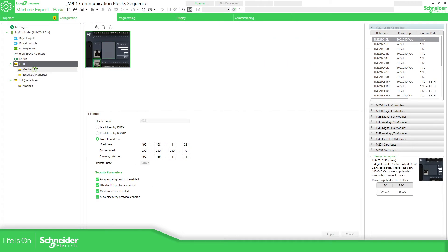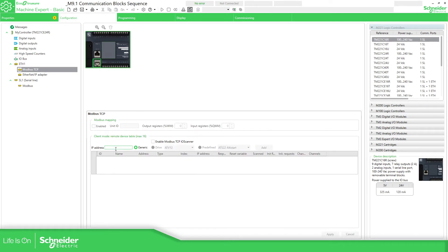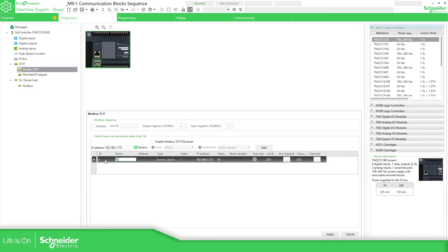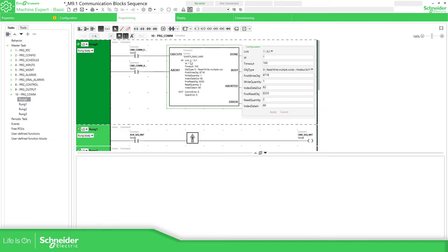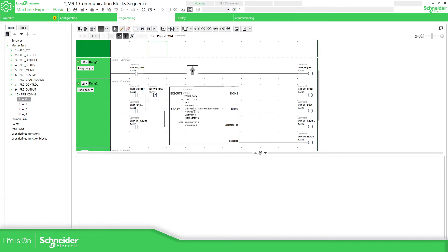For Modbus TCP, we just need to put the IP address of the M172. I'm going to use generic device — there's another way using the TCP/IP I/O scanner which we'll talk about later. Add this device and you can specify the name, for example PLC_M172. You can see there's no serial address here, just the index number one, which will be linked to the ID in the function blocks. The other thing to change on the function blocks is the link — it's no longer the serial line, we need to select the Ethernet port.